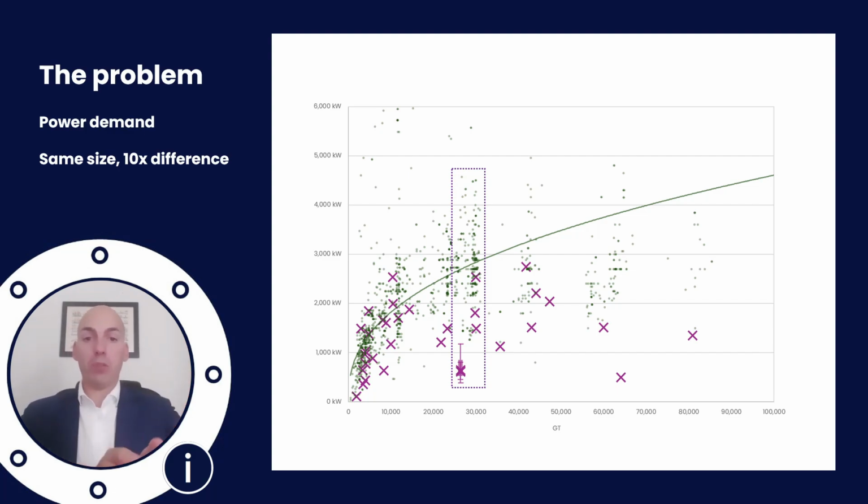So if we have these ships coming at our port, what do we have to design for? Well, the peak powers, we can be sure, can be quite high, 5 megawatts or more. But where exactly is the average? And as you can see, the real-time measured, like a time series domain of these tanker sizes, is actually way lower than what is installed on board the ship itself.